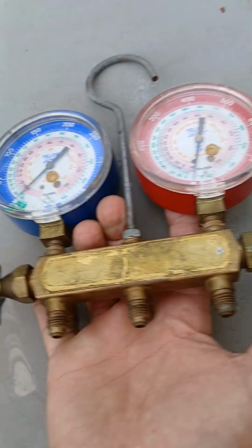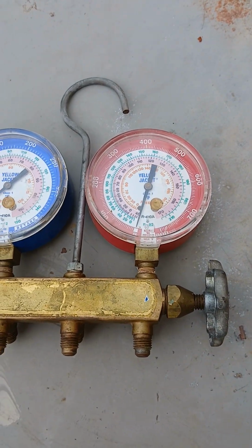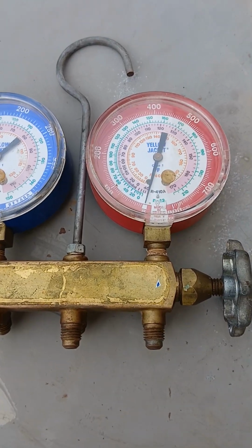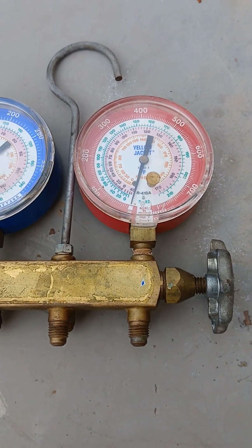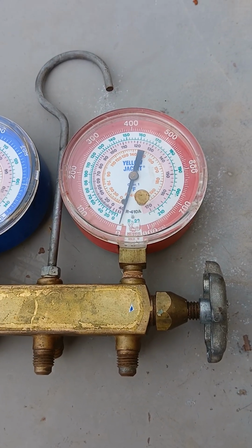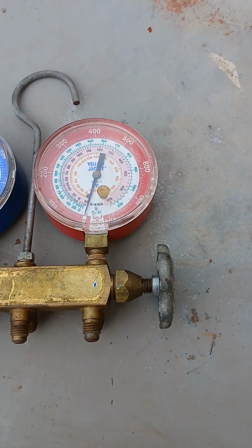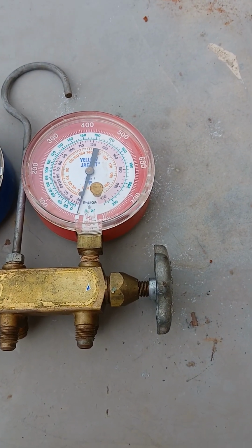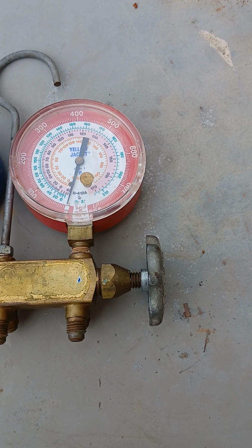With digital gauges, one would hook up their gauge, and once connected, you take the pressure from the outside and cross-reference it. Then you take the gauge temperature minus the line temperature, and one would have to have a temperature clamp on, or some way to detect the temperature of the smaller line. And again, this would be the smaller line.